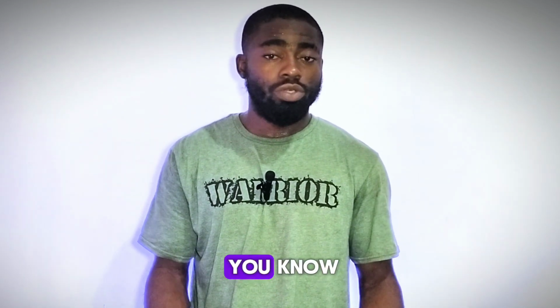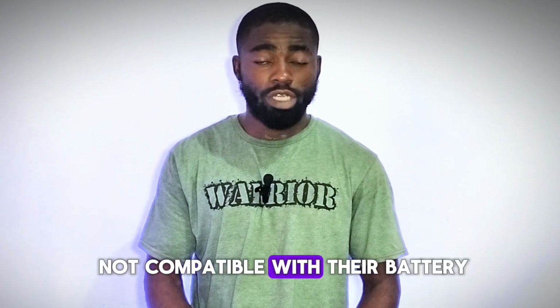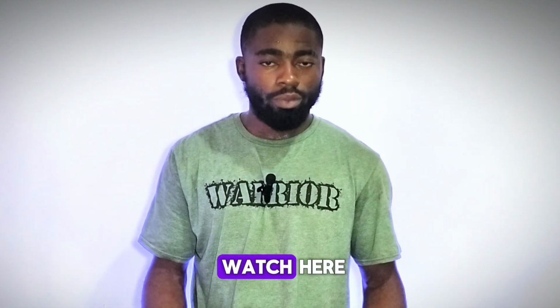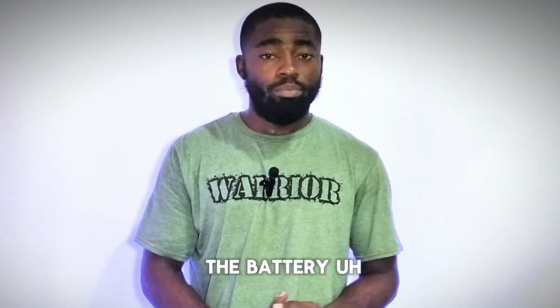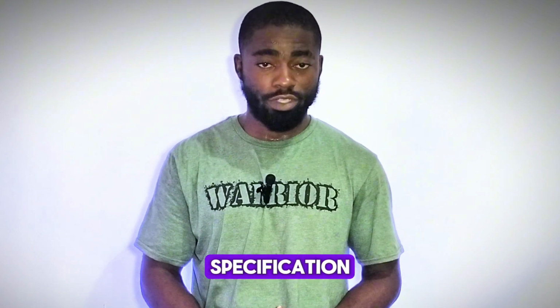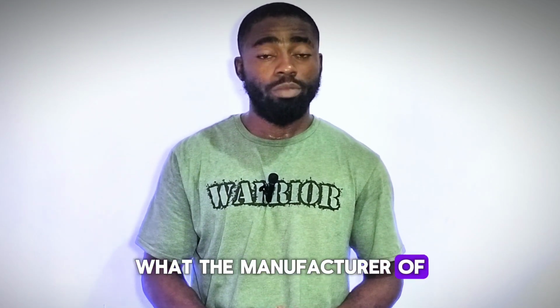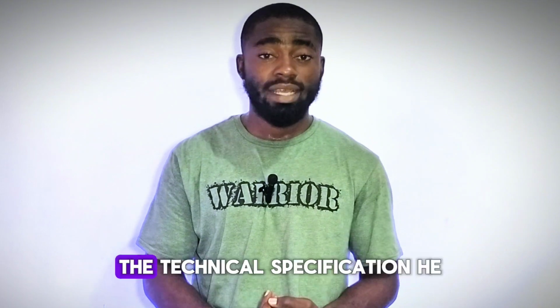And for those whose inverter is not compatible with their battery, you would want to watch here. All you have to do is follow the battery specification — what the manufacturer of the battery recommends. The technical specification he gives out is the setting you should carry out on the inverter.